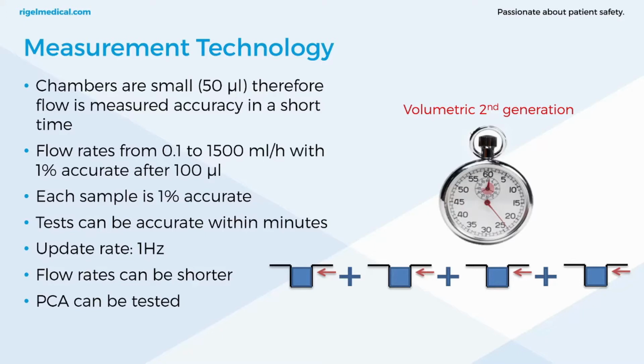Basically, the measurement technology within the Multi-Flo. The chambers are small, 50 microliters. So how does this work? It calculates flow with very small volume measurements over time. Flow is therefore measured accurately in a short time. Flow rates from 0.1 to 1500 ml per hour with a 1% accuracy after 100 microliters. And the reason for this is the 50 microliter chambers. So we need the two samples to produce accurate rates. Tests can be accurate within minutes. Update rate is 1 Hertz. Flow rates can also be shorter, and PCA bolus testing can be carried out.